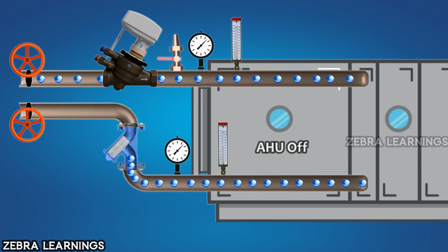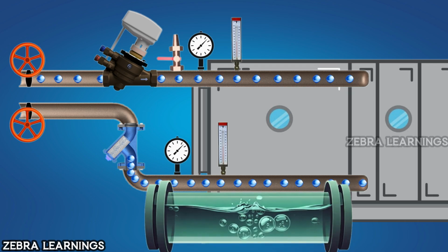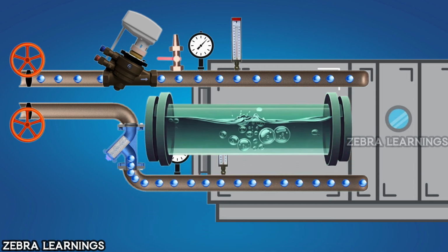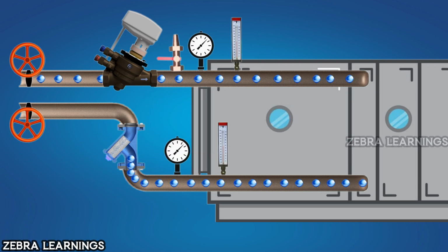Now, since we have opened the strainer, there will be air inside the pipeline. We need to remove this air first. If we open the valve without removing the air, it will create an air lock in the pipeline, and the water flow will be obstructed. Therefore, it is essential to remove the air.